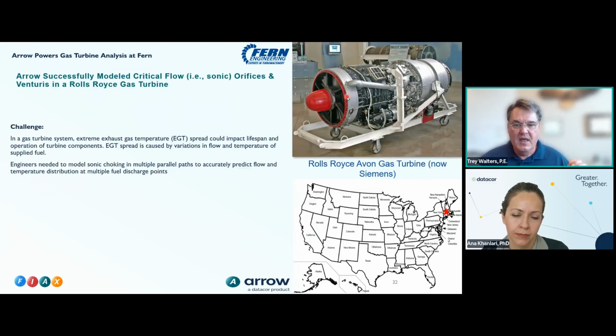You want that to be thermally and fluid and flow balanced. And if it's not thermal and flow balanced around the periphery, it can cause some reliability issues with the turbine, the rotor, et cetera. And so you want to minimize that. And that's what they were trying to do.